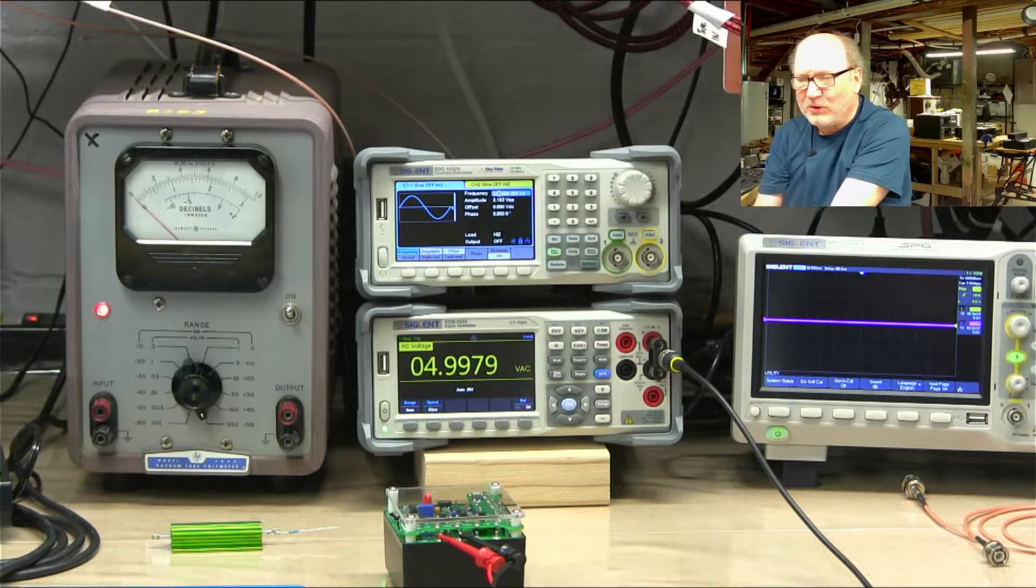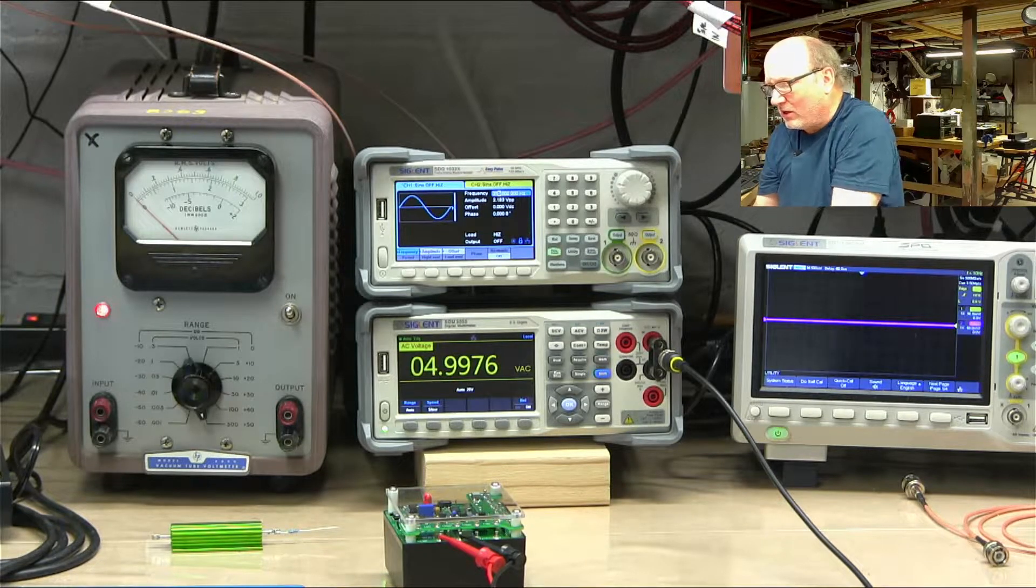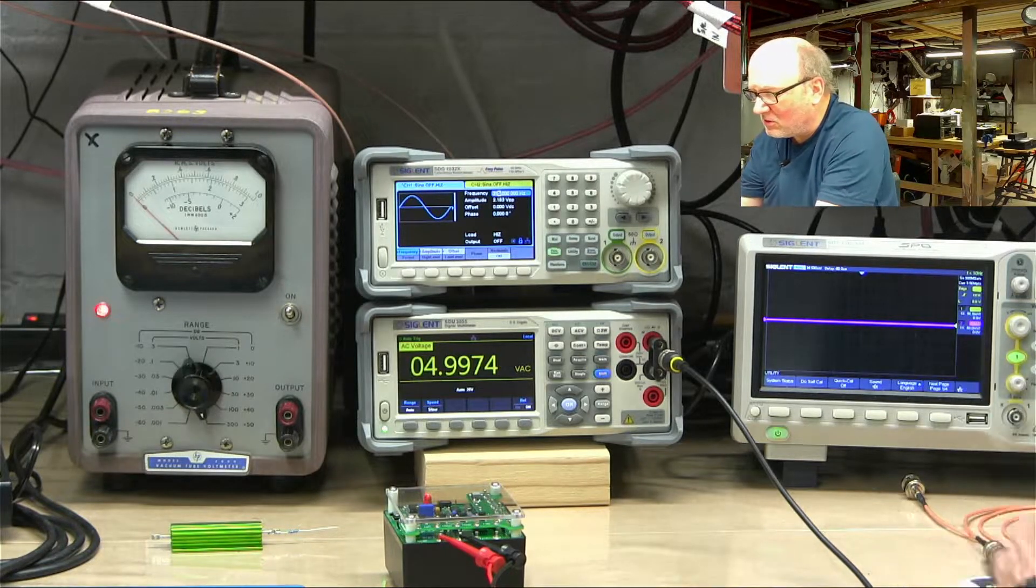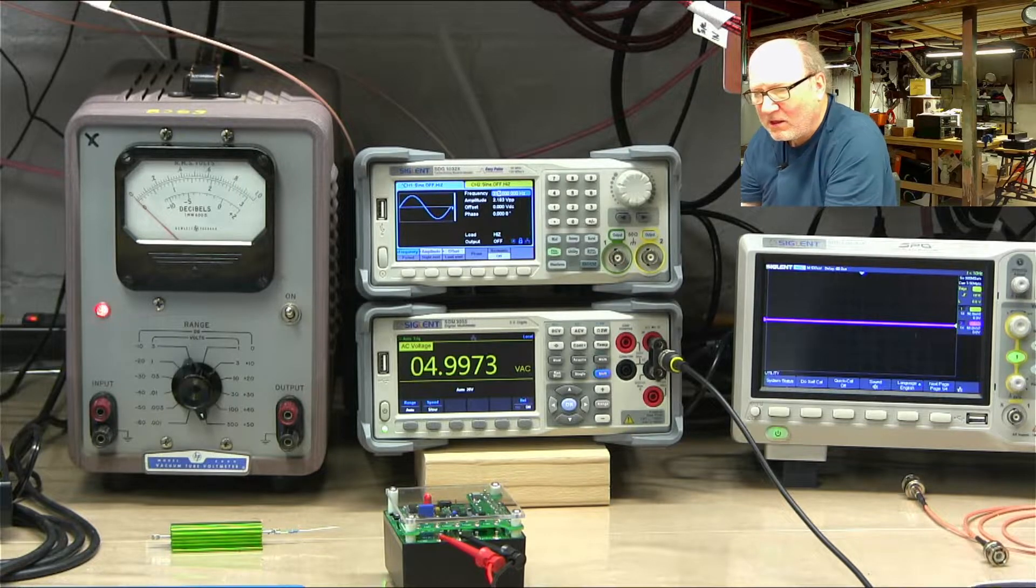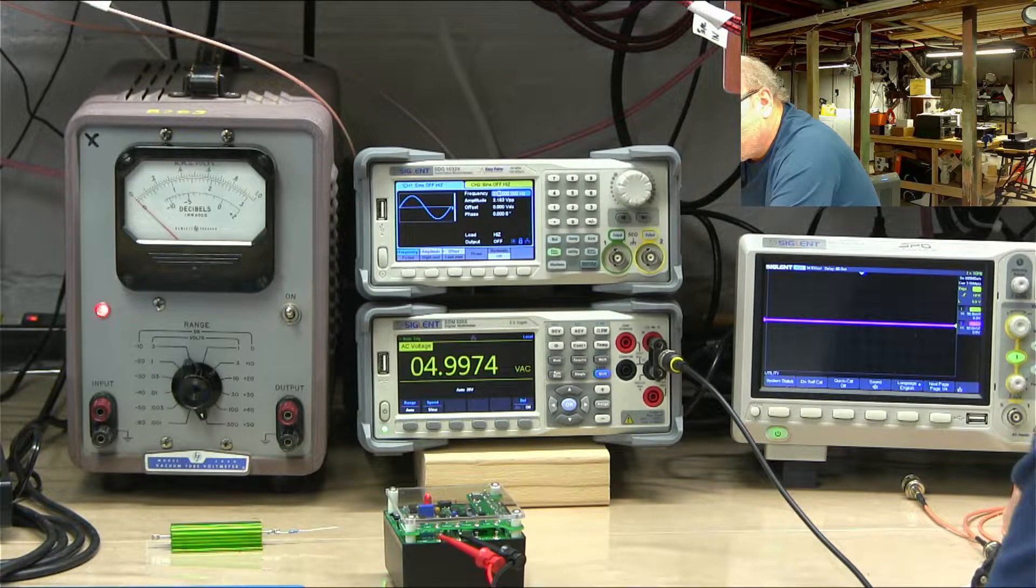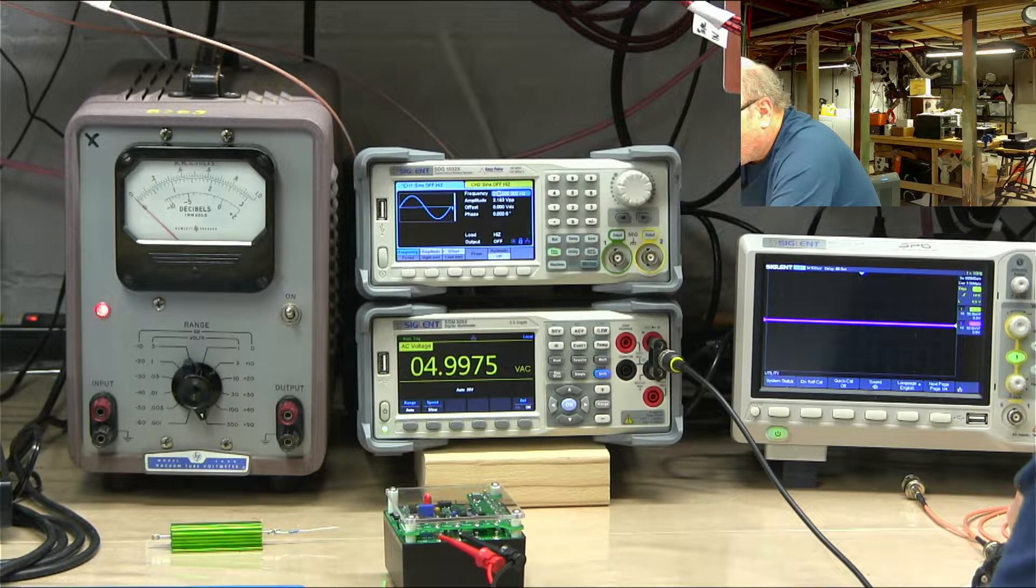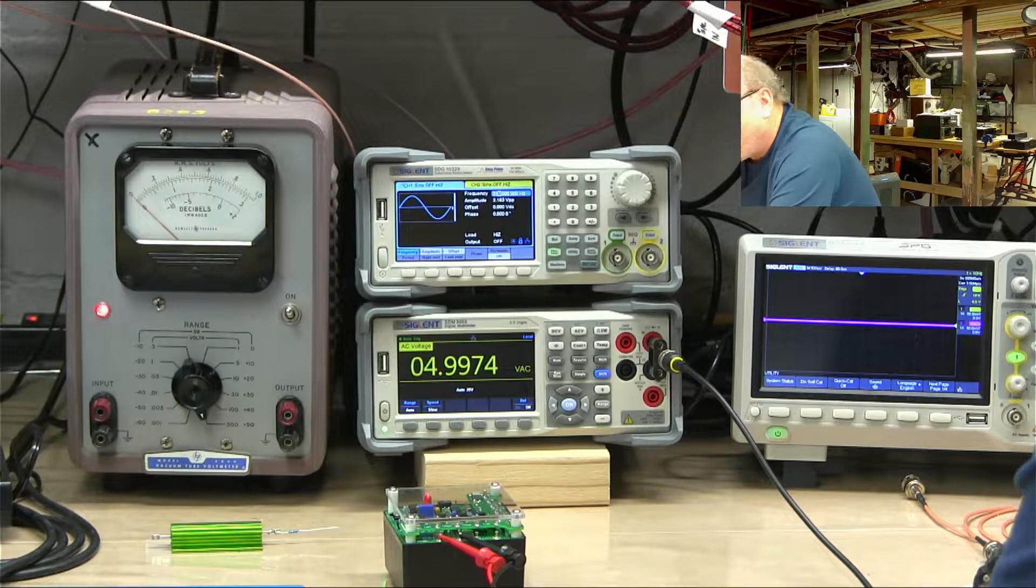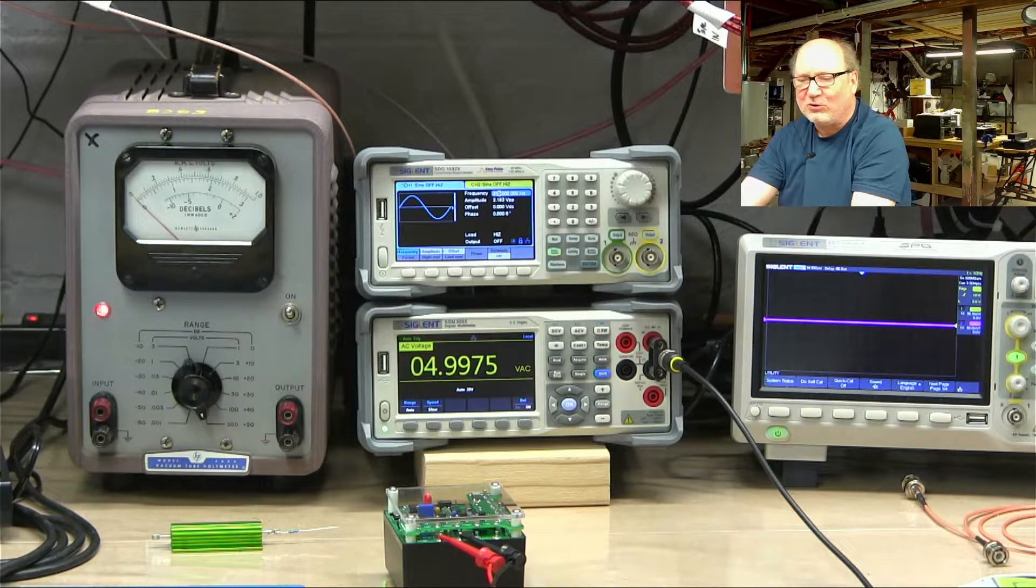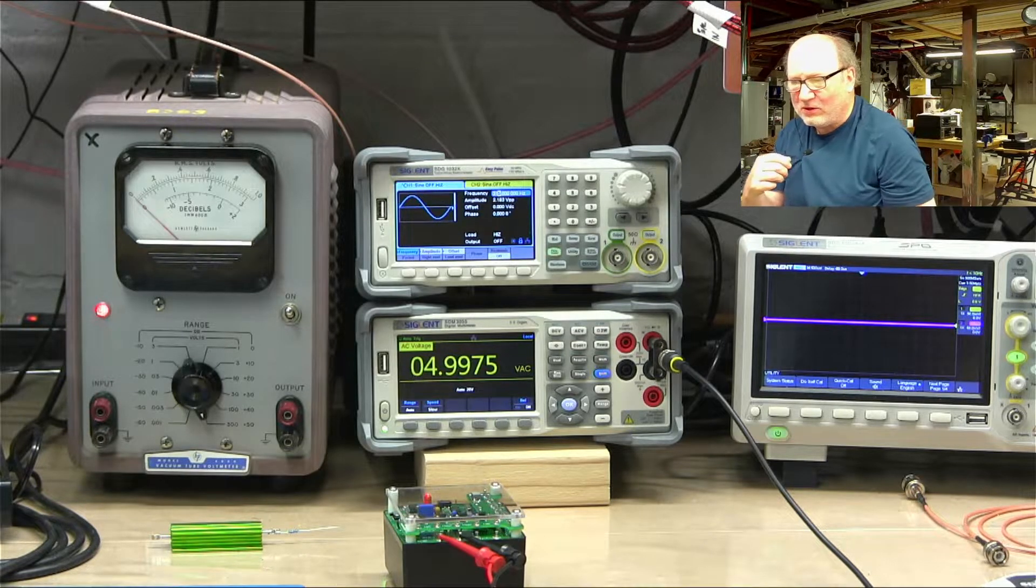So we'll go back to the AC volts. The standard is 4.999 volts and we're reading 4.9975, so we're reading roughly about 0.0015 off. The tolerance on the AC was 0.02, so the meter has to be plus minus 0.02, and we're well within 0.02.